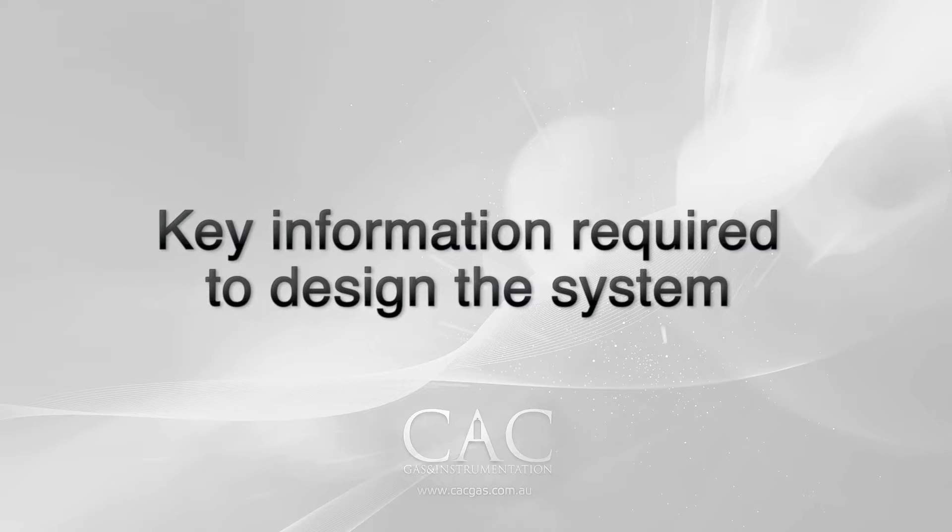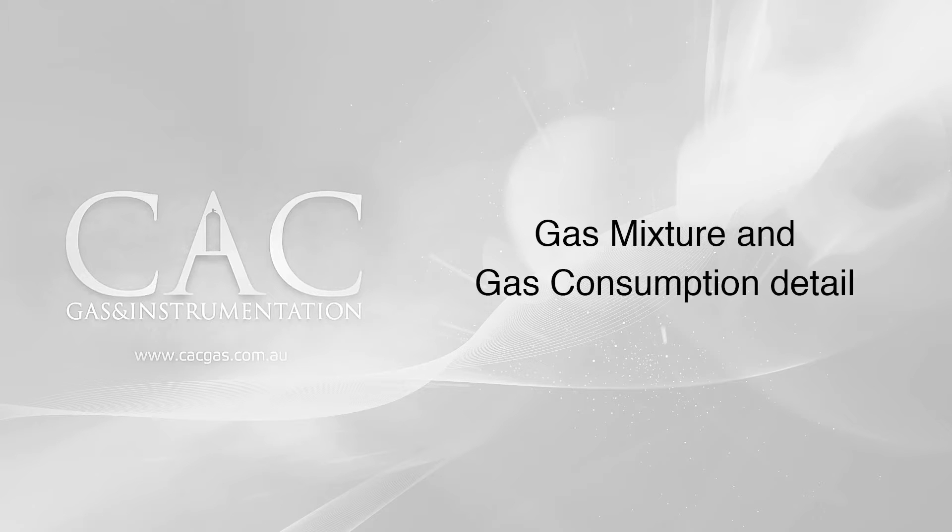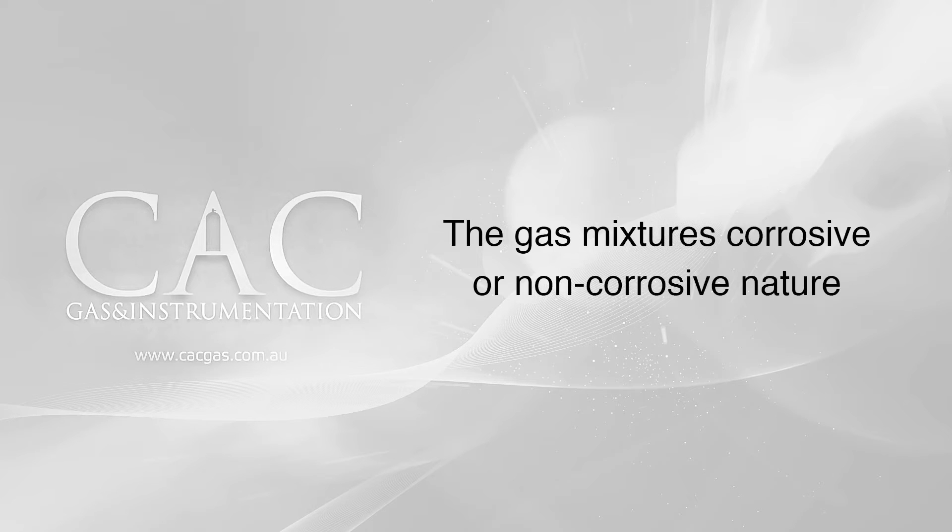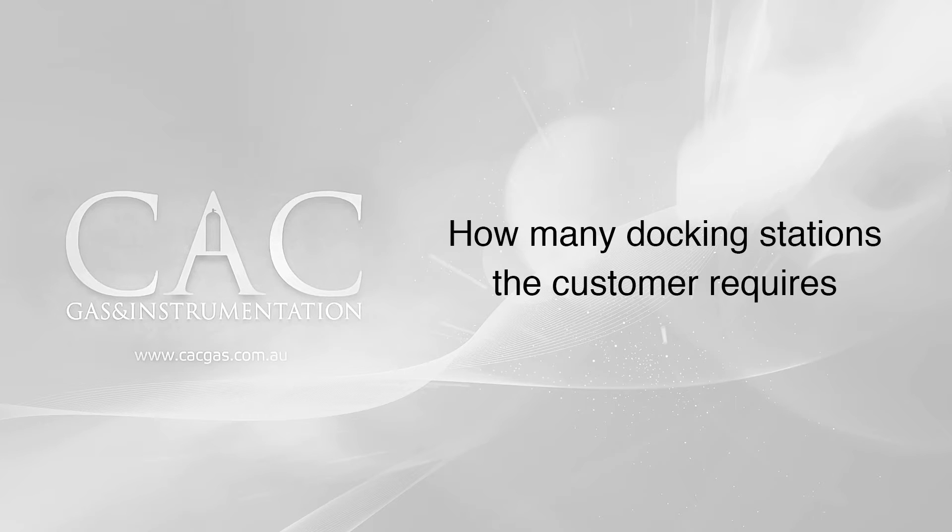The key information that is required to design the system includes gas mixture and gas consumption detail, customer calibration and bump test procedures or protocols, the gas mixture's corrosive nature or non-corrosive nature, the distance of the gas cylinders to the docking stations and how many docking stations the customer requires.